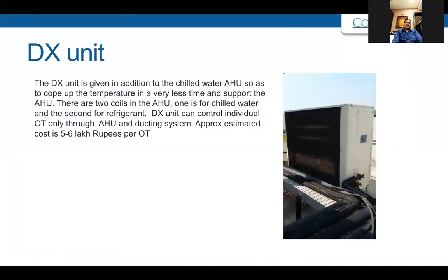So another aspect is called a DX unit, which we had recommended earlier when the World Bank projects started coming in, along with a small AHU, which helps the smaller OTs to survive. It costs around 5 to 6 lakhs per OT. It can actually satisfy all the NABH conditions in terms of air velocity, air changes, everything. So most of the taluk hospitals in Tamil Nadu and Kerala have adopted this DX unit design. It gives you flexibility to achieve temperature changes very fast.